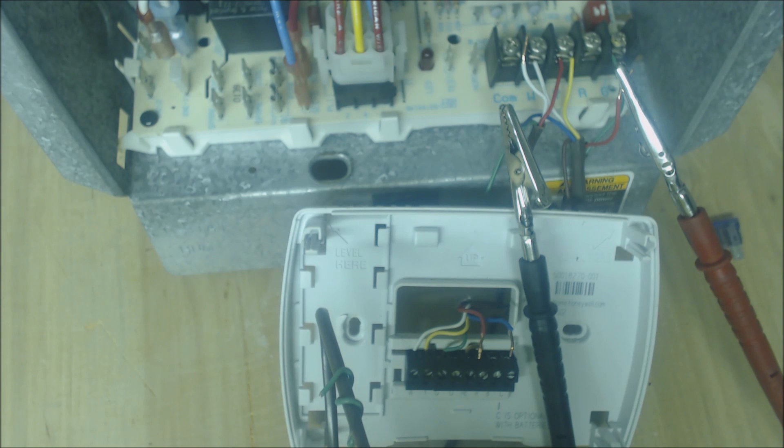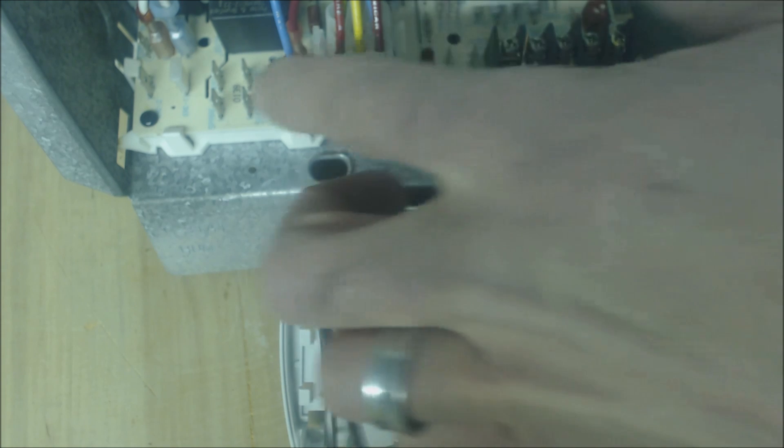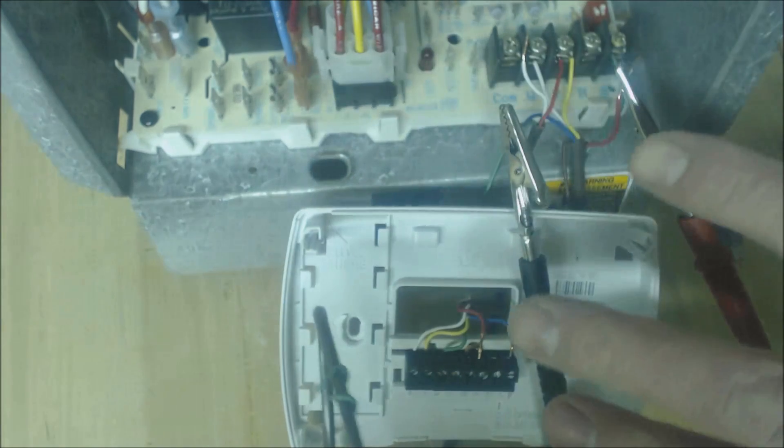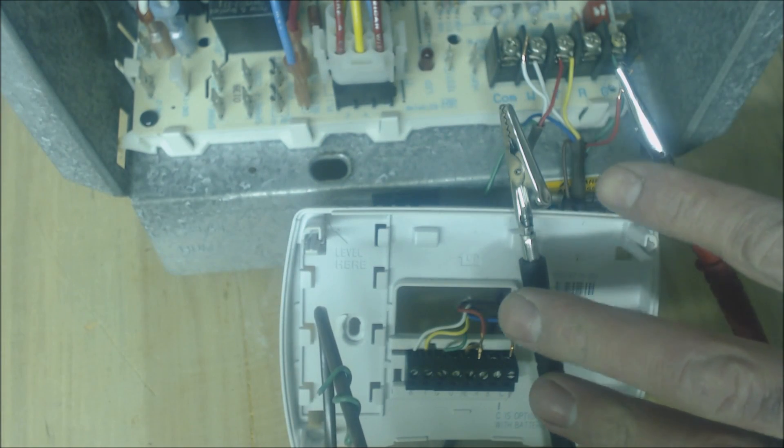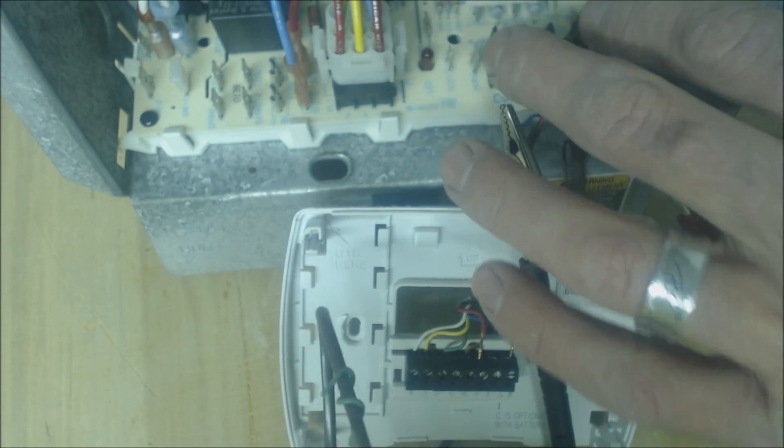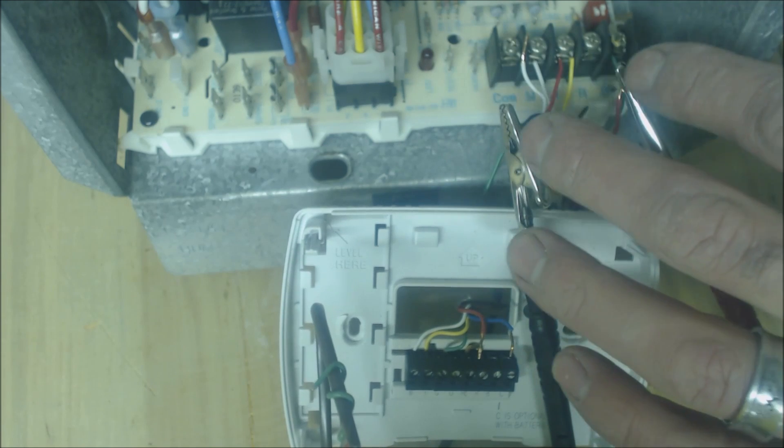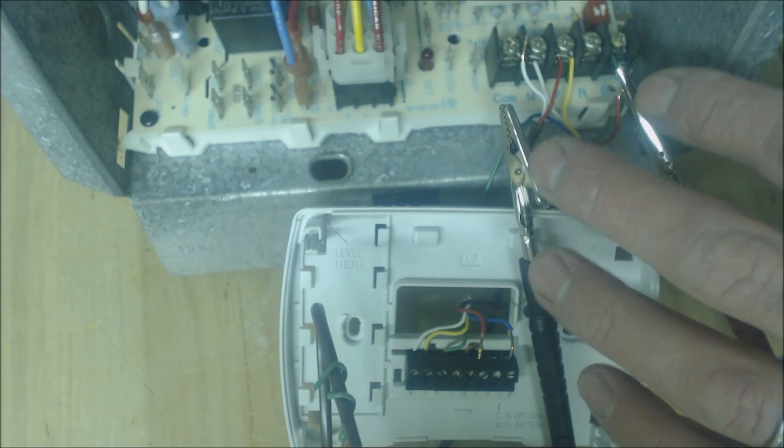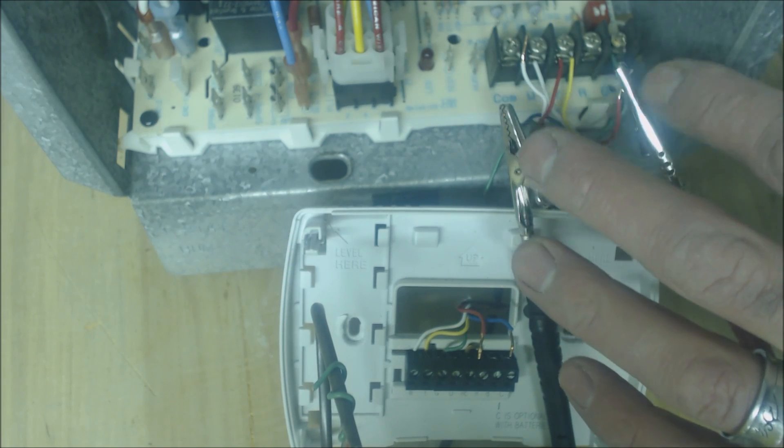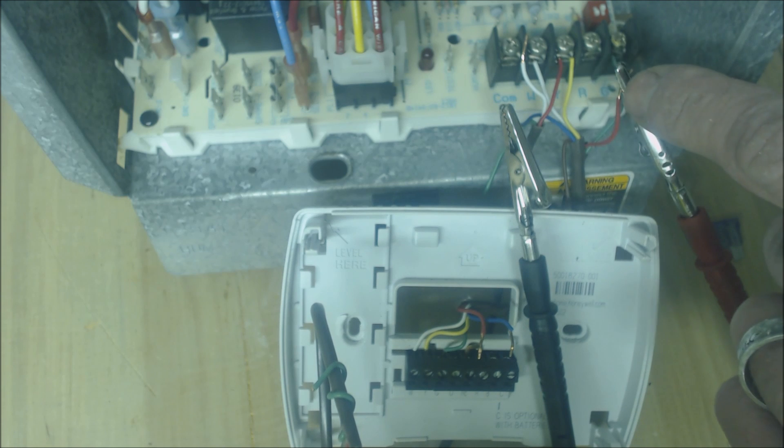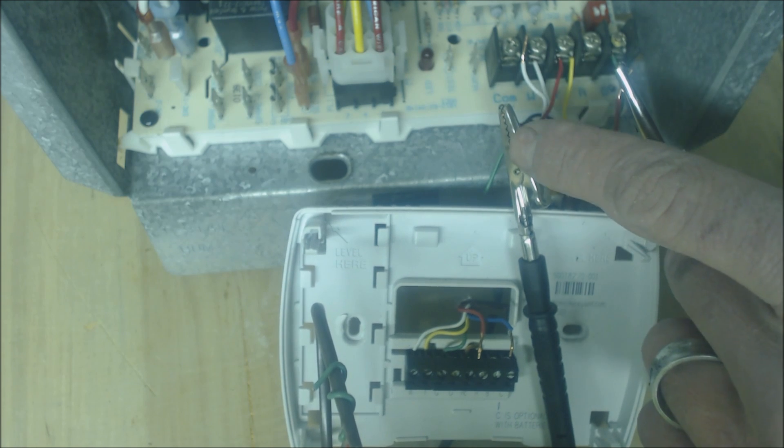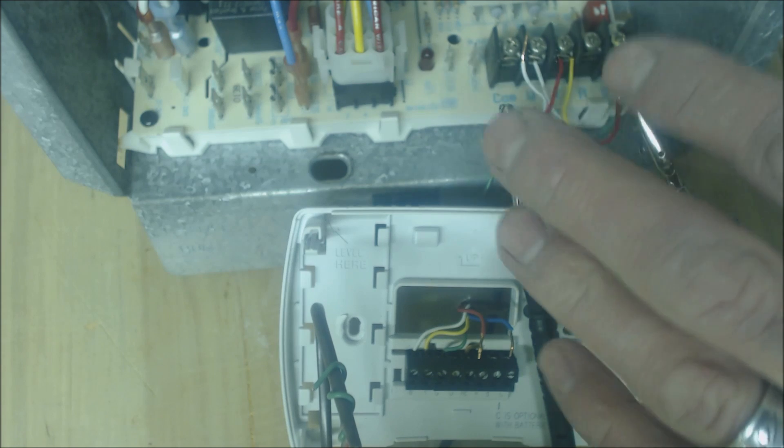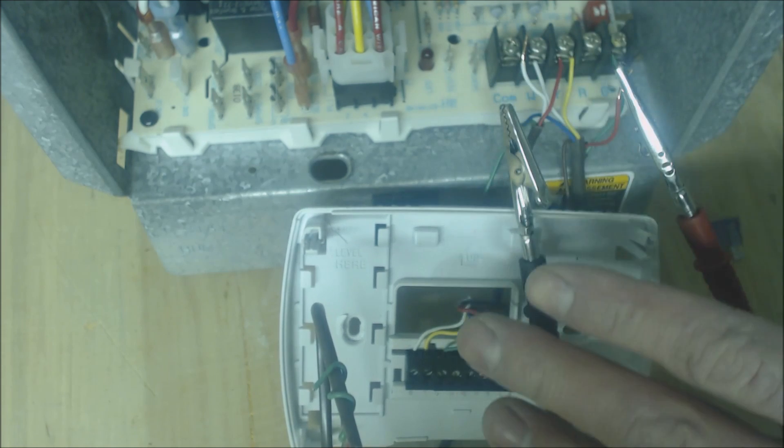You could choose to run a new thermostat wire because you know that the fuse was blown because of the thermostat wire at this point. After you've disconnected it from the furnace control board or the air handler control board and you still have a resistance reading between the wire that was hooked to the R and the wire that was hooked to the common, then you know that it's in the thermostat wiring.